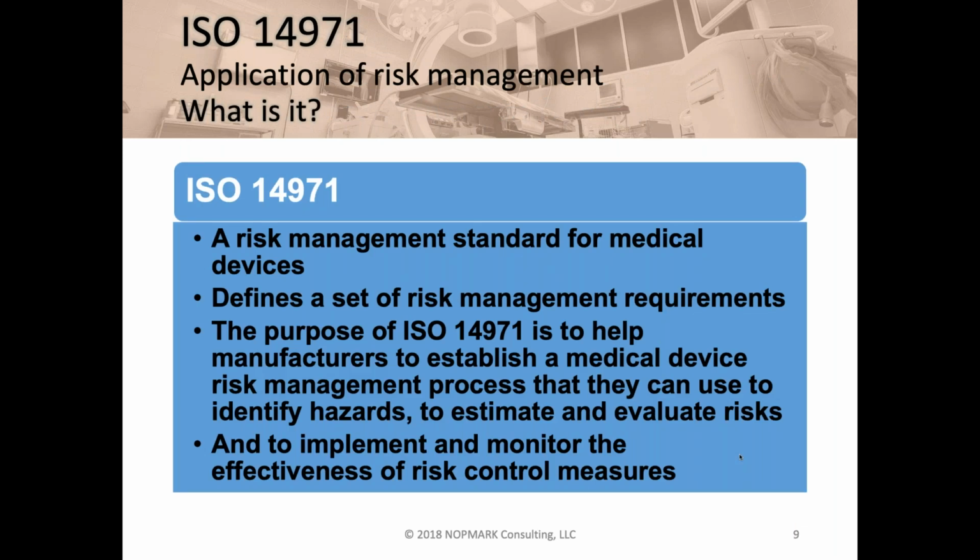So let's look now at a second of those quality system standards. This one is called ISO 14971. This is sometimes referred to as the big risk one. Almost all of the regulations that you will see in the medical device world start off focused on this topic of risk: harm to the patient, harm to the user, harm to the environment. So this aspect of product risk to those users is really a focus point of these standards.